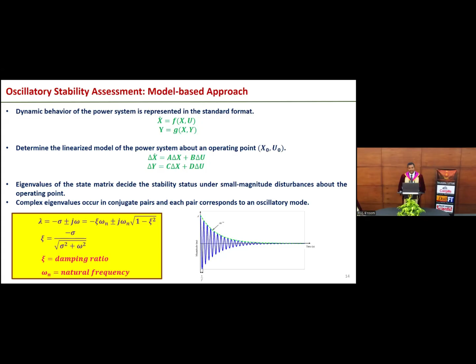So this is the traditional approach for oscillatory stability assessment in power systems. But this traditional approach may not be suitable when the scale of the system gets larger and larger, so there are different measurement-based techniques. In this case, we capture the waveform and process the data over a data window using signal processing to determine the frequencies of the oscillatory modes and their dampings, and determine whether the system has adequate oscillatory stability status.